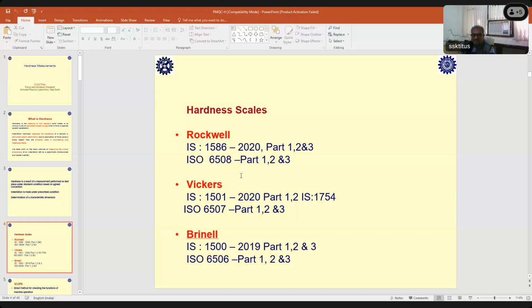All these things are very tightly prescribed in part 3, especially for the calibration machine, and most of the NMIs will have machines which comply with this particular part 3. So that is very, very important. When we have a machine which complies with the requirements of the part 3 standard, then we can use that machine for calibrating standard hardness blocks. So that block will become a kind of reference material.